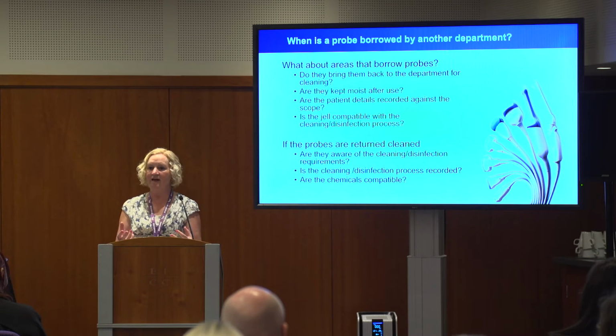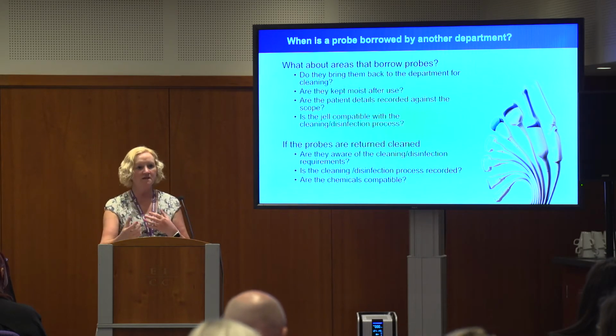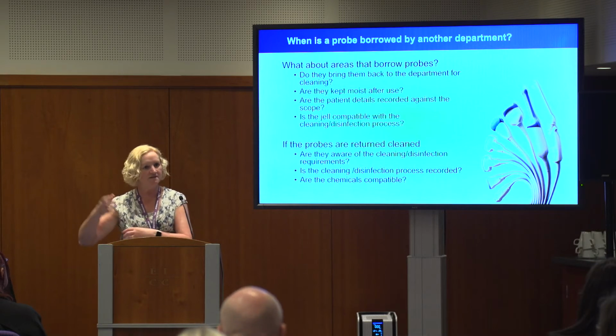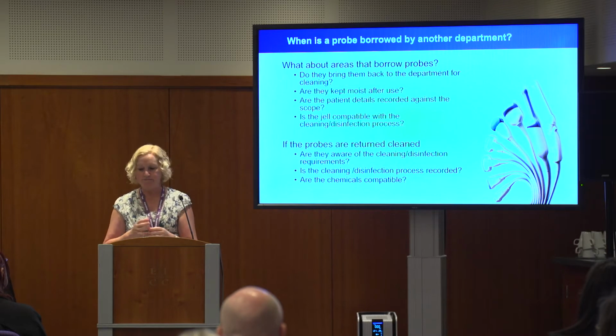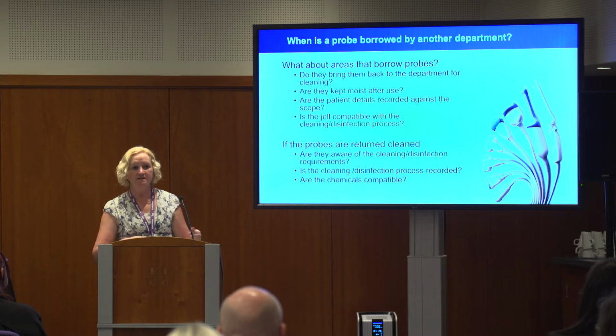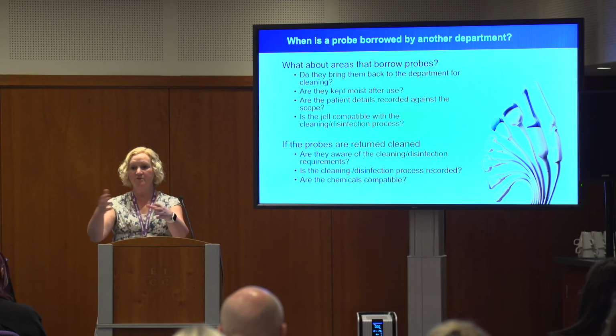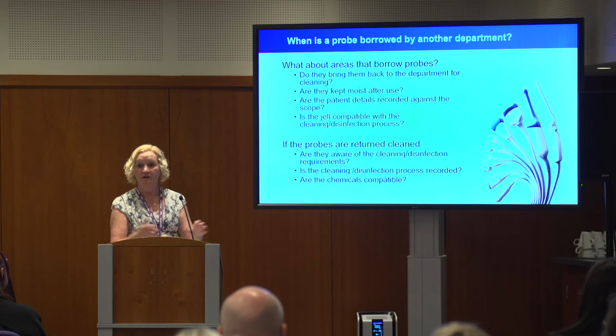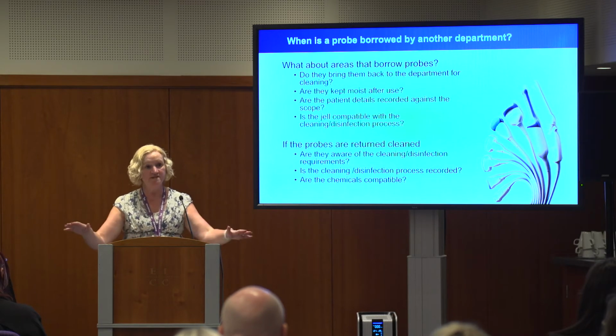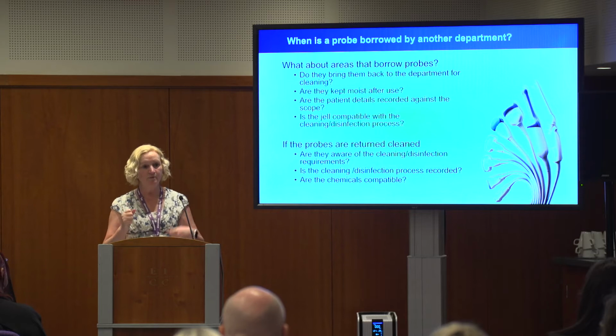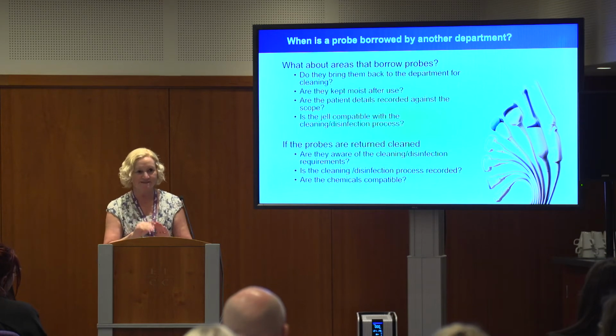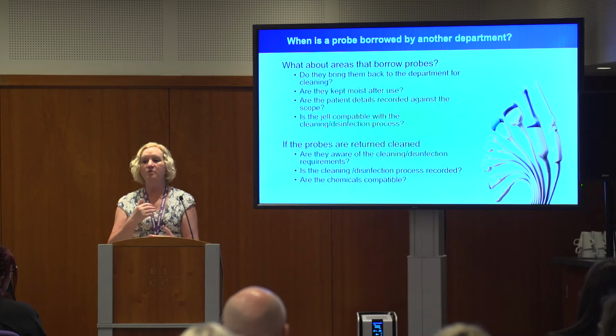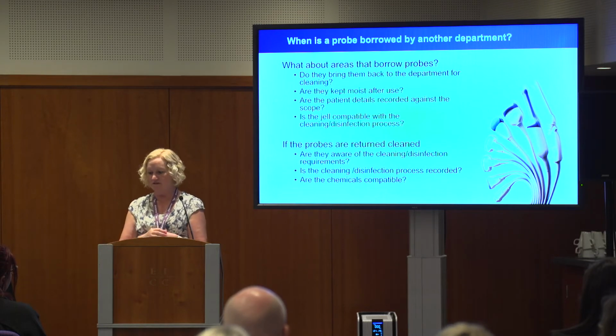If they're cleaning, are they aware of what needs to be done? Sort of from clean to dirty, are they aware of that? Or do they go from dirty to clean and contaminate your lead, where you're going to handle it to plug it into the machine? Do they have a method of cleaning? Do they work from dirty to clean when they're cleaning, so they're not putting a clean scope in the same area that they put the dirty scope? I've seen people have a dirty probe come in, put a piece of blue paper down, put the probe on that, clean it, take that blue paper out and put it down on the same place on the counter. So obviously contamination, bugs, do not go through that bit of blue paper. That's enough to keep it safe. So are you sure that if you're loaning your scope, they're cleaning it properly? It's not coming back to you contaminated and putting you and your staff at risk.